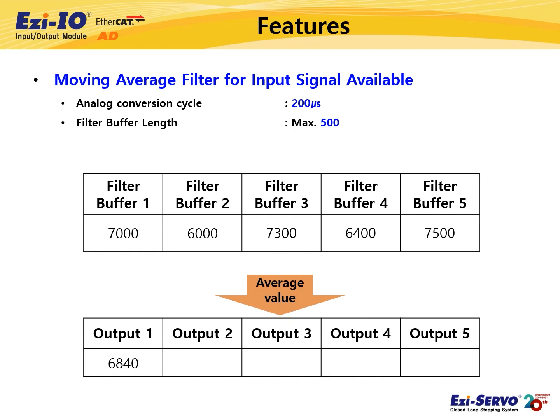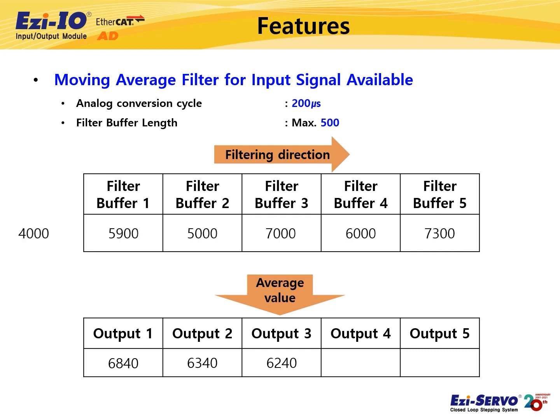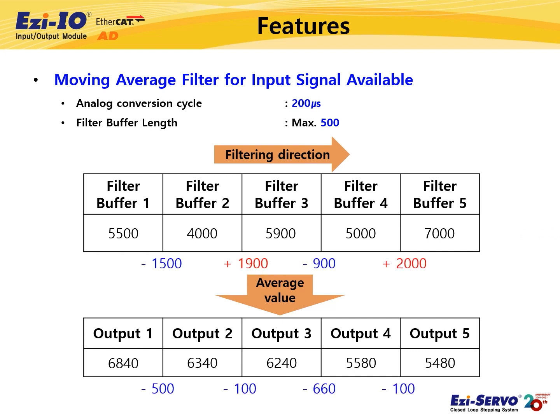New input data is saved in the filter buffer. When the next sampling data is input, the oldest data is deleted and the new input data is saved in the buffer in order, and the average value of the 5 input values is calculated. You can see that the differences between the values are smaller when the moving average filter is applied.